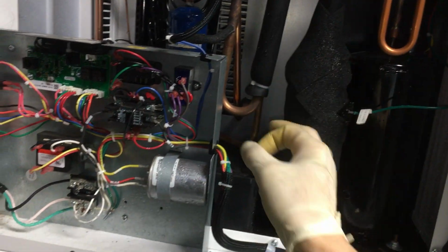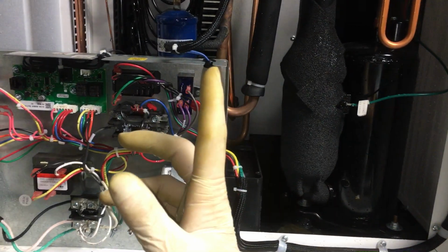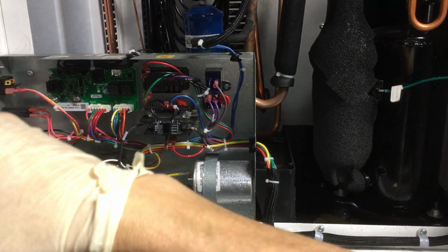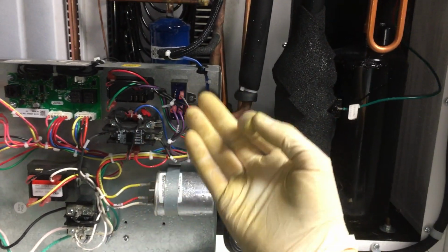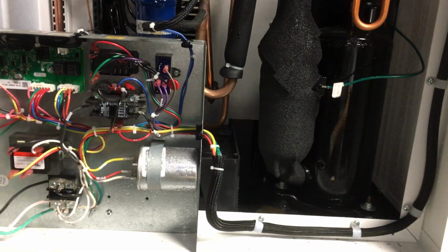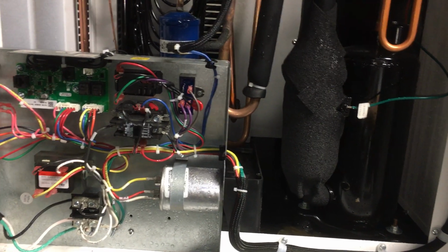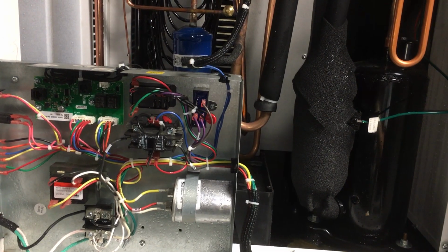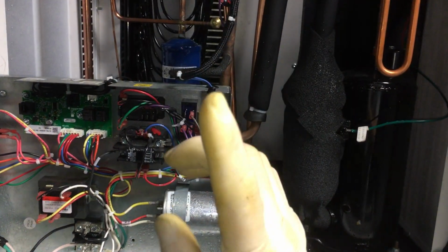Now, I take that reheat gas and I run it into a plate heat exchanger to heat water. So now I have a large tank of nothing but water, just a simple tank, not expensive, not complicated, a simple insulated tank of hot water that gets heated by the waste gas from cooling the processing room, to cool all the equipment, all the electrical components that need to be cooled in that room, that normally would go to the atmosphere. It just gets rerouted into water, and now you have this large tank of hot water.